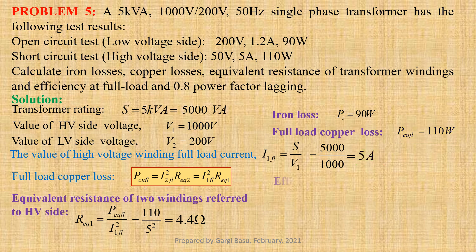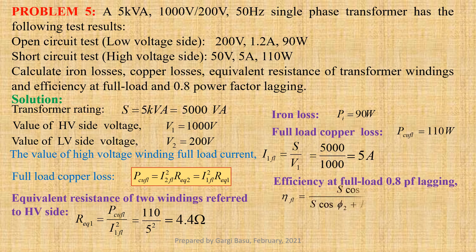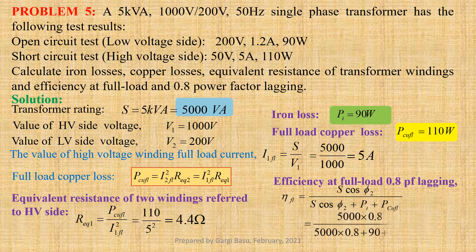Now let us calculate the efficiency at full load and 0.8 lagging power factor. ETA_FL equals to S cos phi 2 divided by S cos phi 2 plus P_I plus P_copper_FL, putting values we get 5000 into 0.8 divided by 5000 into 0.8 plus 90 plus 110, that gives us 95.2381 percent.